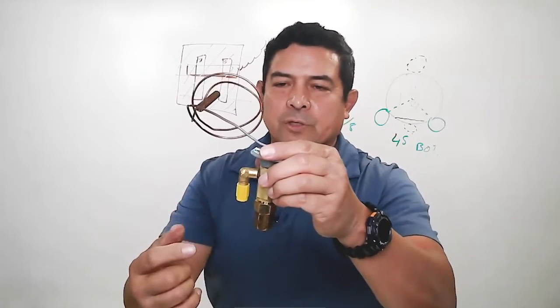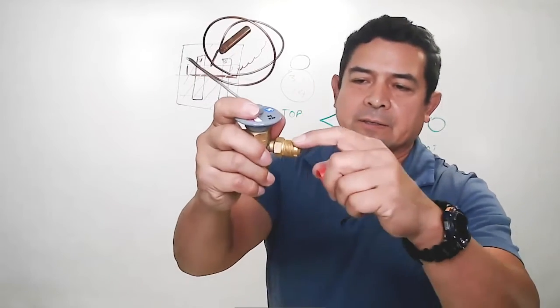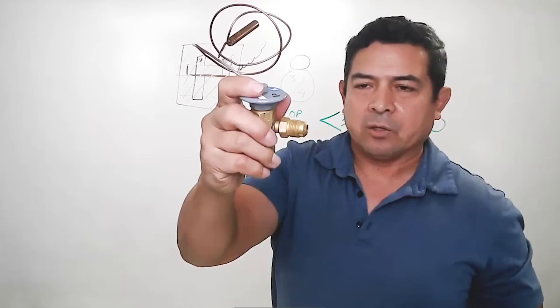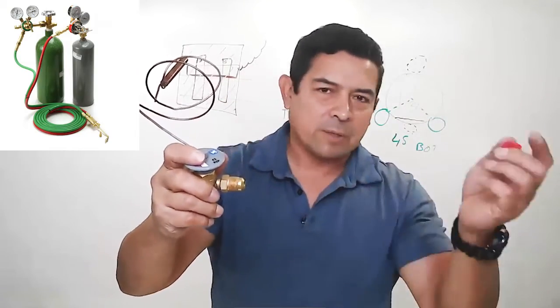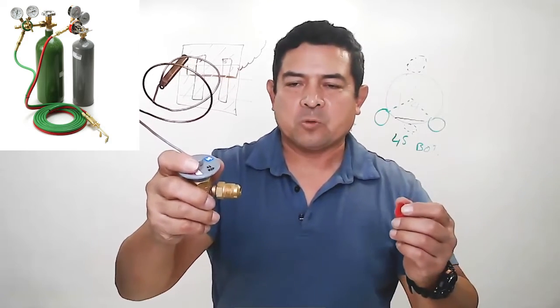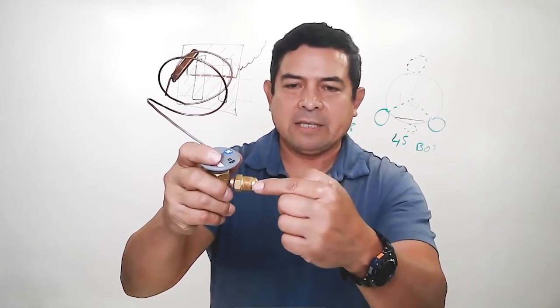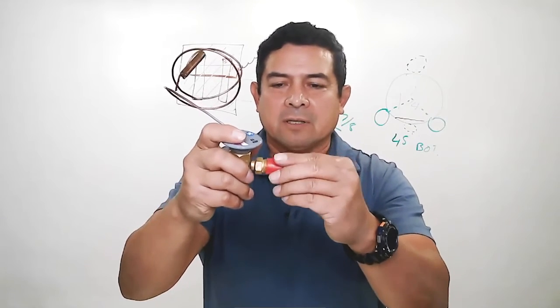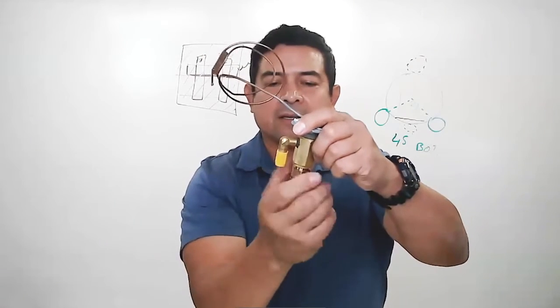If these were not threaded, if this was sweat, in other words, you're going to use your torch and you get some silphos, your oxy acetylene rig, or some of you like the turbo torch, whichever, you're going to have to heat this up so you can melt the silphos. To do that, well, guess what? You're going to have to take this apart.